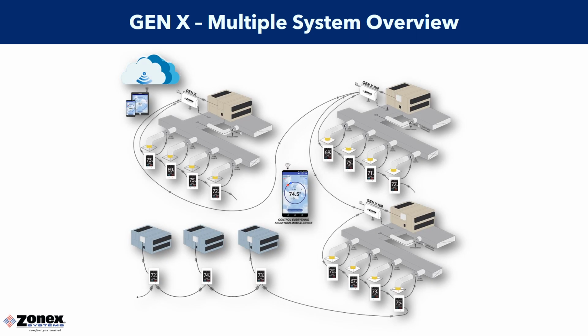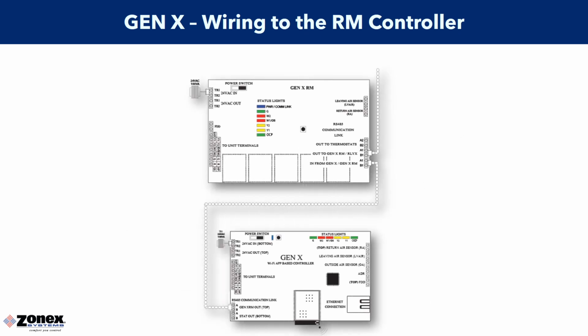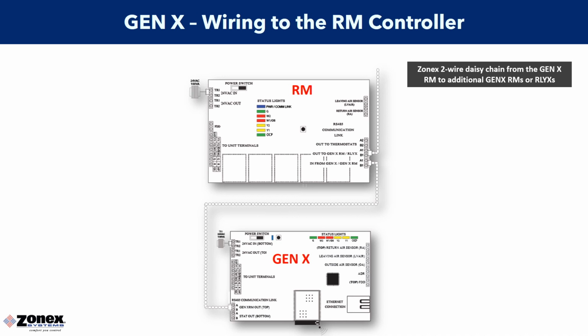Here is a bird's eye view of the Zonex control system working with additional zone rooftop units utilizing the Zonex RM controllers. The GEN X is the central control point and communicates to the Zonex RM controllers over the RS-485 communication. Here we have an overview of the Zonex control system wiring into additional RM controllers. Utilizing the Zonex communication cable, you will wire in at the bottom left-hand corner on the A and B terminals of the GEN X controller, and you will daisy chain that to your Zonex RM A and B1 terminals in the bottom right-hand corner. For additional Zonex RMs, you will wire out on the A and B terminal out, and you will continue daisy chaining your Zonex RMs together in this fashion.